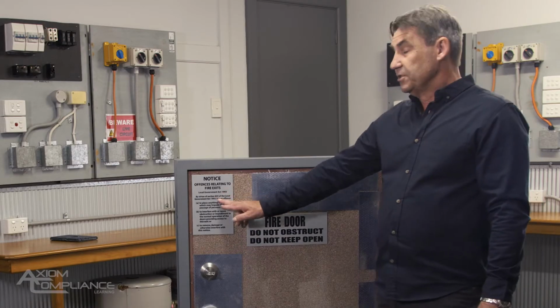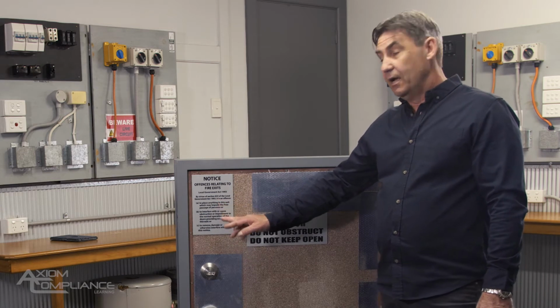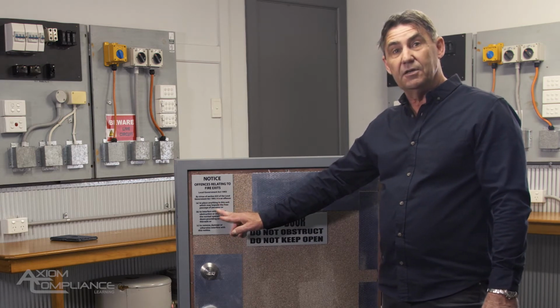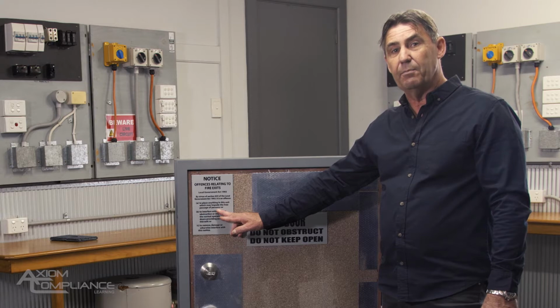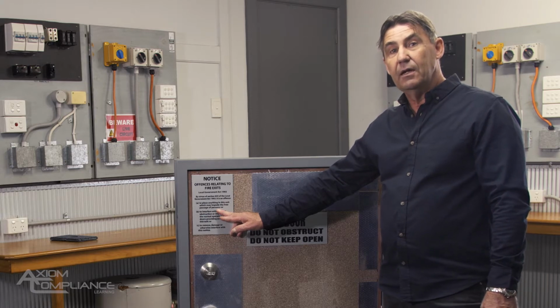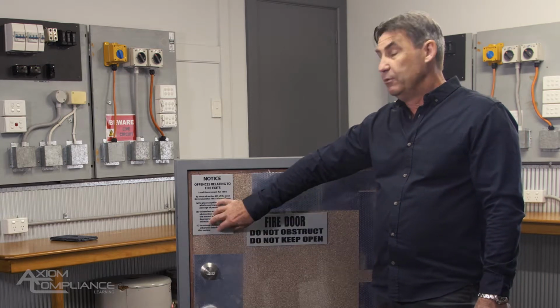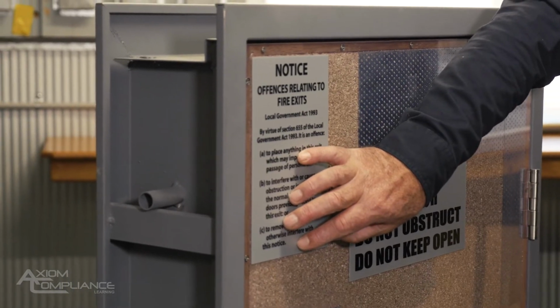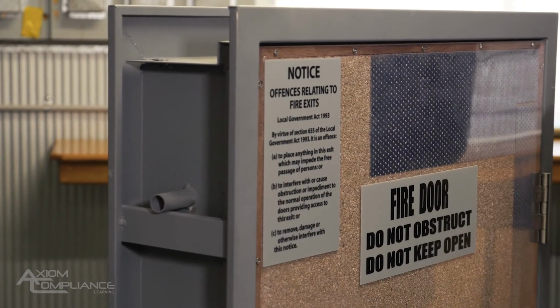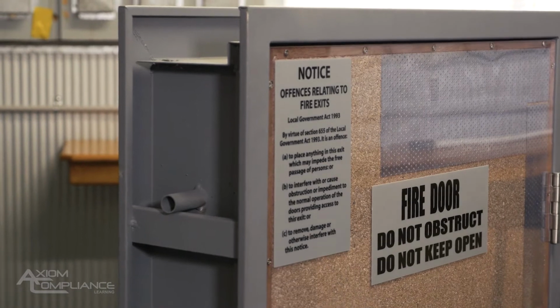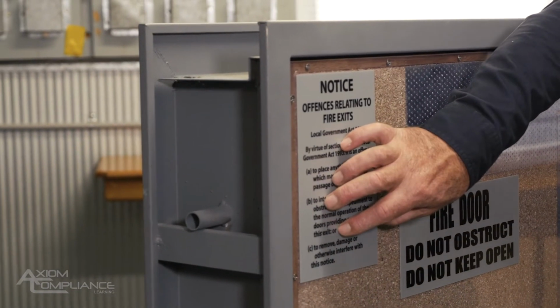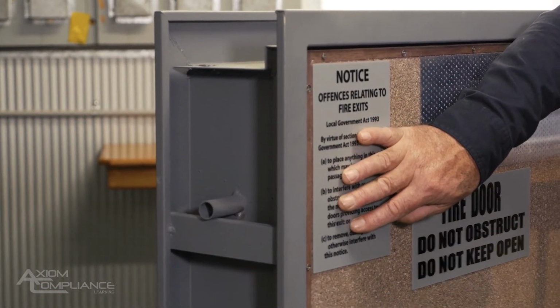There's another signage which is called statutory signage, and it's an offence to block a fire door or to stop the path of egress out of a building. And we have to clearly label and tell people that it is an offence to do that. And for this type of door where we're egressing into an open space, once again, this statutory signage is required on both sides of the door.